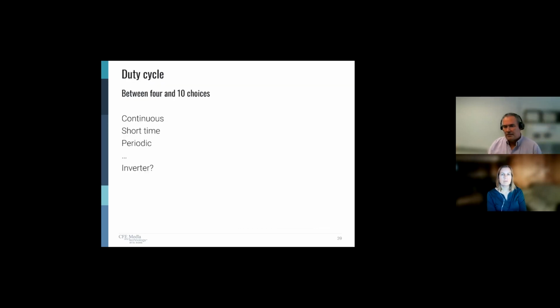Duty cycle. Depending on who you ask, there are between 4 and 10 choices, and I think this list changes almost on a weekly basis. What we're most likely to run across is what we call continuous duty. You start the motor, it runs forever. You don't ever shut it off, or nearly shut it off. There's a short duty cycle motor. Again, that's a rapid stop, start kind of thing. Periodic, it starts every 5 minutes and stops every 5 minutes.